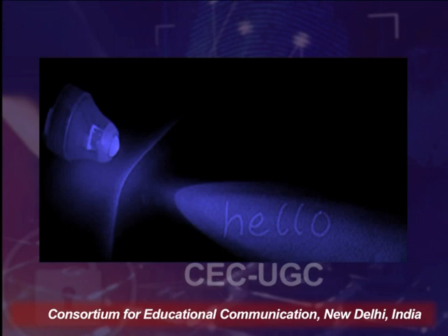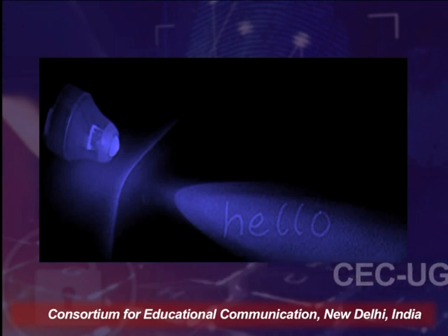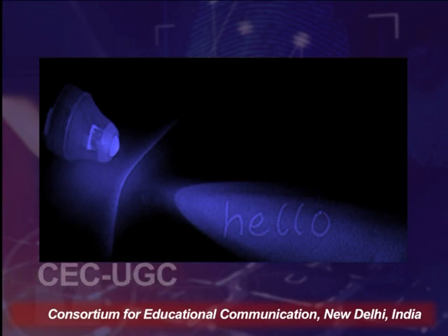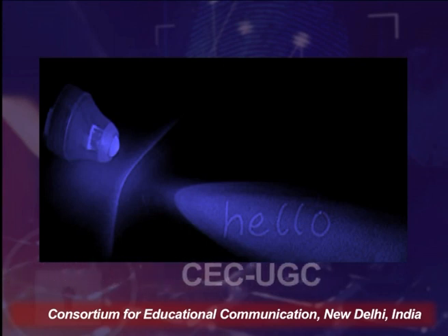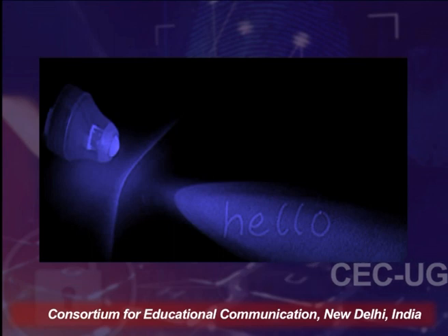All of these can illuminate the document from above, and we also have the option of transmitted light in the VSC, which can offer UV light at 365 nanometer. Another source present inside the VSC is a flash tube which has a range of 850 to 1100 nanometer and is used for the anti-Stokes flash function. With a UV light source, if there is any secret handwriting written with any chemical material, for example lemon juice, it is visible either under heat or under the light sources.